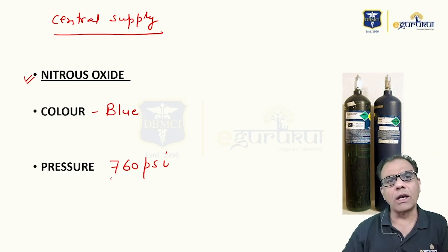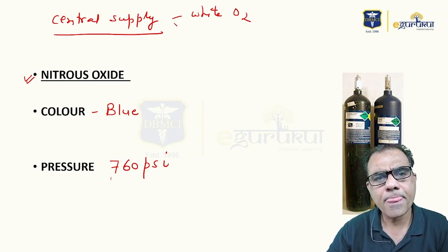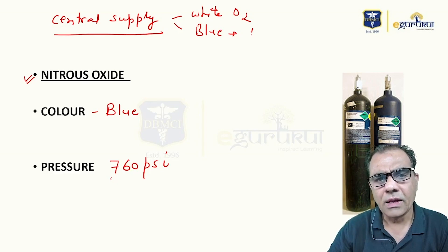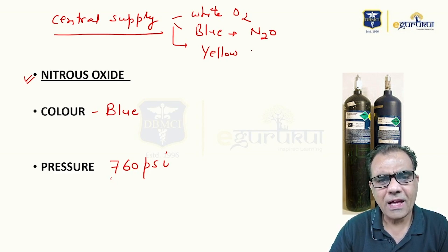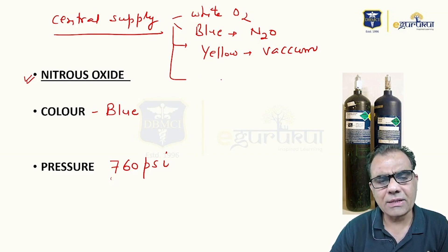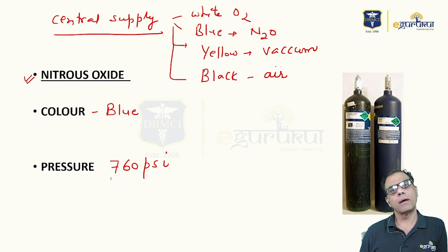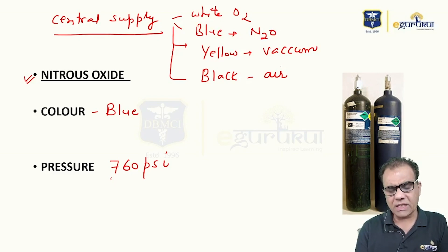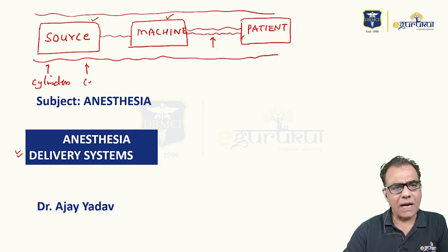Through central supply there is also color coding. You will see a white color pipe for oxygen, a blue color pipe for nitrous oxide, yellow for vacuum or central suction, and black for air. Sources of gases can be cylinders or central supply.